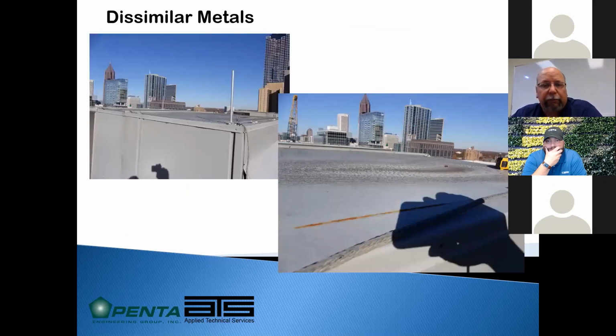One of the other things we routinely see is a lot of architects will spec a copper system, and copper does last longer than aluminum, but it doesn't play nice with a lot of metals. We get what's called galvanic corrosion when we have contact of copper with dissimilar metals. In this instance, this was a tin-plated copper conductor connected to aluminum air terminals. But everywhere this copper conductor was in contact with the mechanical unit, it started rusting out.